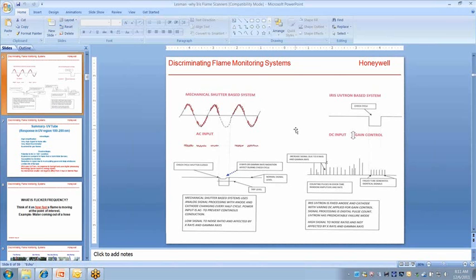They are not subject to vibration. The only time they will fail is if you subject the unit to higher heat than the rated ambient temperature. So if the ambient temperature is rated at 158 Fahrenheit and you are operating at 170 or 180 degrees Fahrenheit, then the sensors will get damaged, and some other equipment inside the viewing head might get damaged because of the higher temperature. Like everything else, higher temperature will do that. On a UV tube, we can run the tube at a very high temperature, up to 300 degrees Fahrenheit.